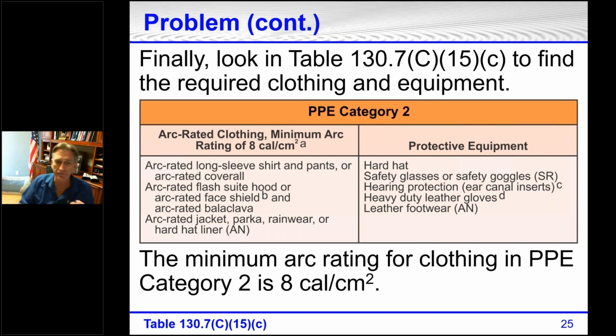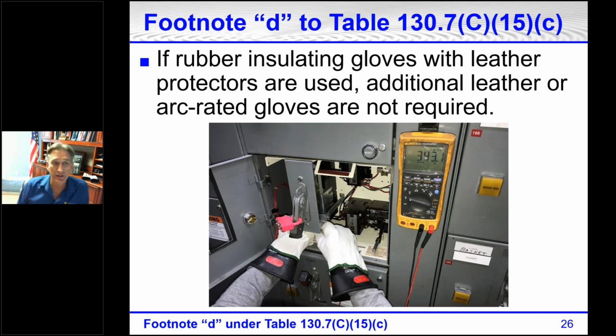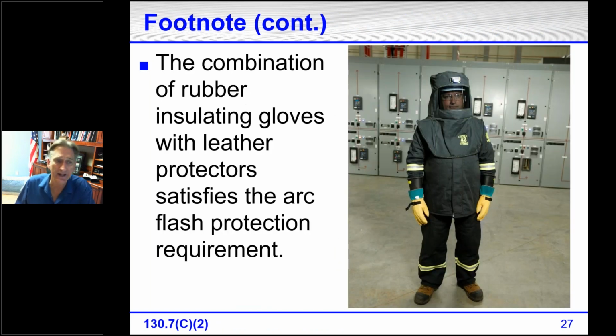Well, there's a footnote that goes with that, footnote D. And footnote D says, if rubber insulating gloves with leather protectors are used, additional leather or arc-rated gloves are not required. What this means, if you are wearing rubber gloves with leather protectors, that takes the place of having to have heavy-duty leather gloves. It takes the place of having to wear arc-rated gloves in accordance with that table. So the combination of rubber insulating gloves with leather protectors satisfies the arc flash protection requirement.